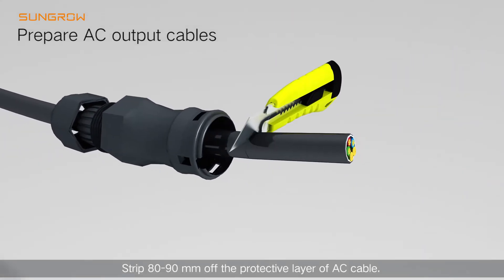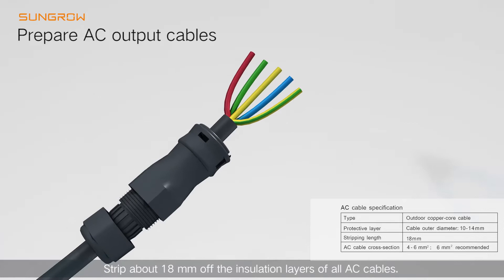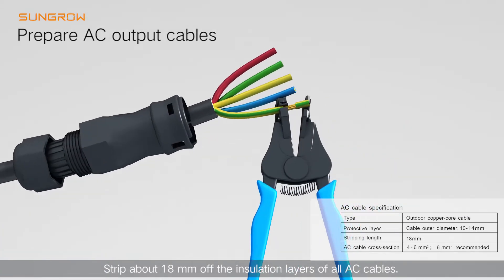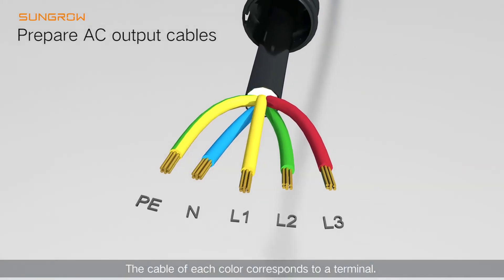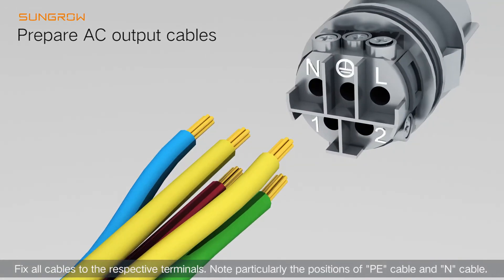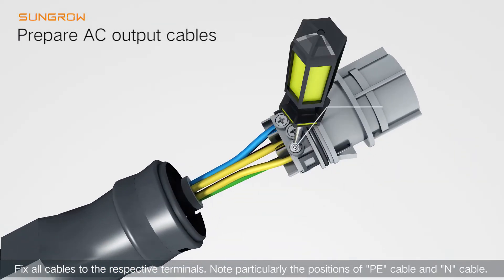Strip 80 to 90 mm off the protective layer of the AC cable. Strip about 18 mm off the insulation layers of all AC cables. The cable of each color corresponds to a terminal. Fix all cables to the respective terminals. Note particularly the positions of the PE cable and N-cable.